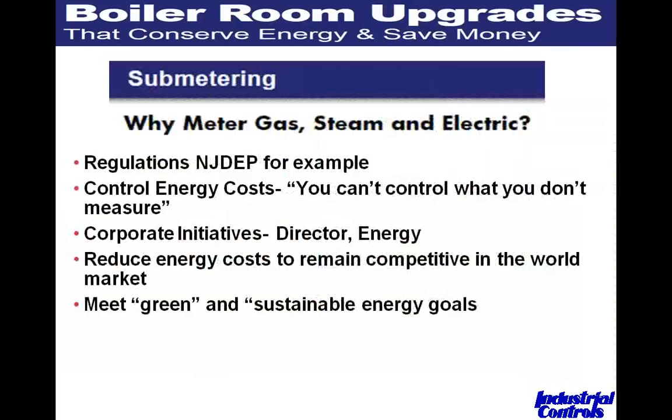So why sub-meter gas, steam, and electric? The first reason is regulatory compliance. In New Jersey, the NJDEP three years ago required anyone with energy-producing devices of 20 million BTUs or more to perform a combustion test annually and report the previous year's gas or oil usage. Two years ago it went to 10 million BTUs, and in 2010 it went to 5 million — equivalent to about a 150 horsepower boiler. We're also getting calls from New York State, suggesting they may have passed a similar ordinance.